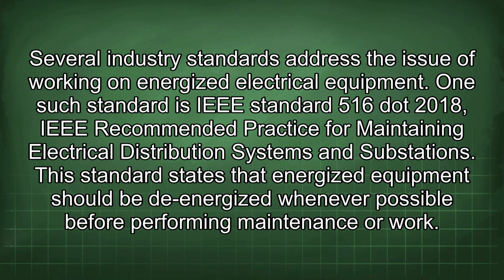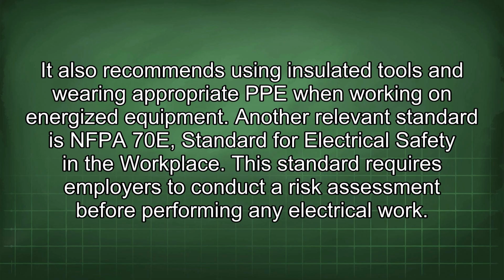Several industry standards address the issue of working on energized electrical equipment. One such standard is IEEE Standard 516-2018, IEEE Recommended Practice for Maintaining Electrical Distribution Systems and Substations. This standard states that energized equipment should be de-energized whenever possible before performing maintenance or work. It also recommends using insulated tools and wearing appropriate PPE when working on energized equipment.